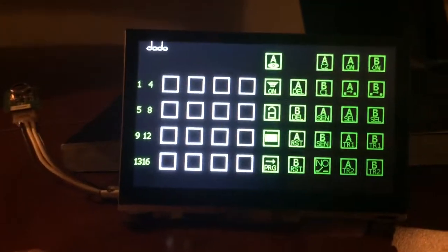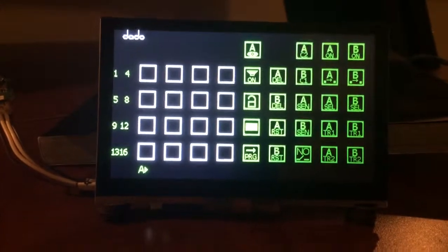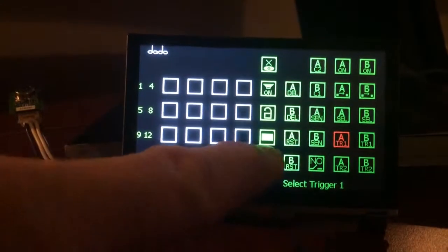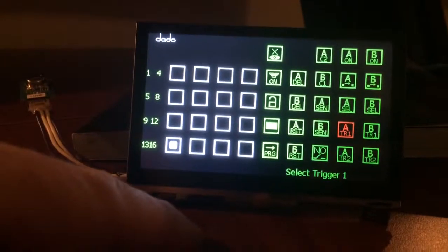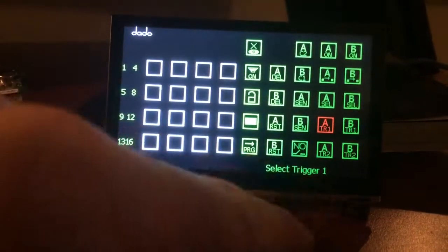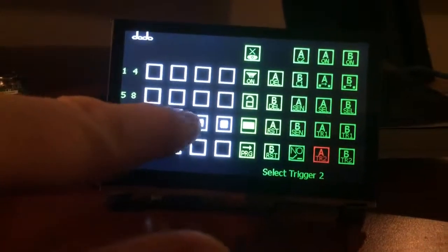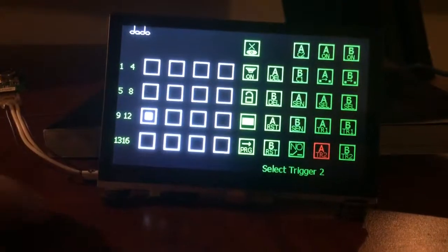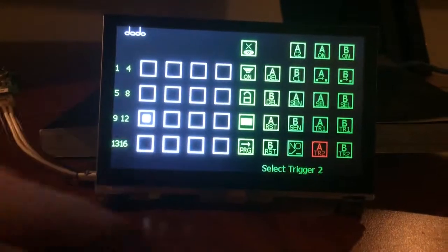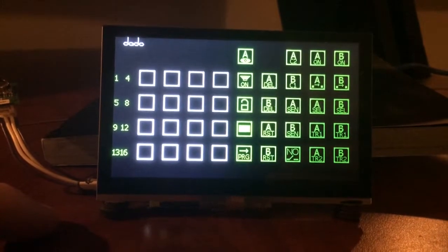So in other words, traffic moving towards the door could fire the door to open. Traffic moving away from the door wouldn't cause it to open. And these can be precise areas. Let's say that this is a congested area and we only want specific foot traffic to fire the door. So let's go down and select just a very specific region: trigger one is here, trigger two is here. So it will go back to its typical watching mode.